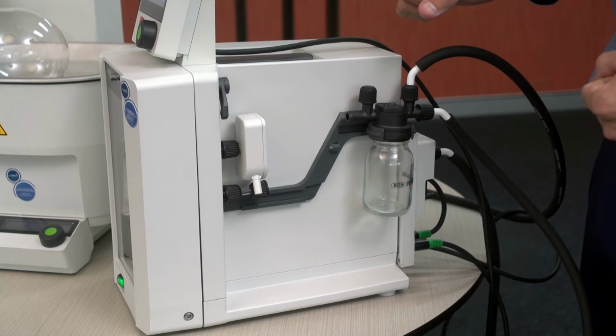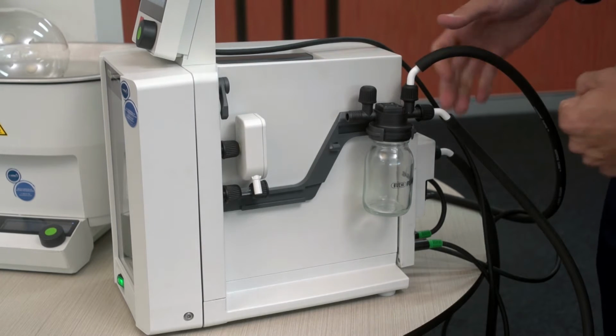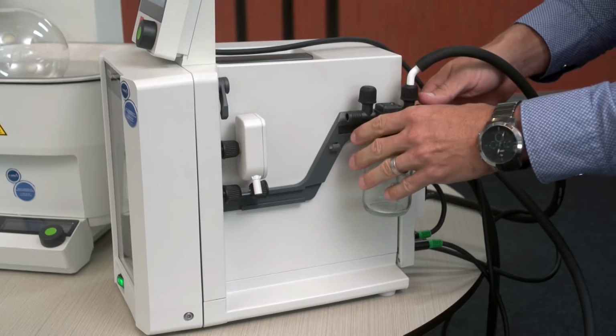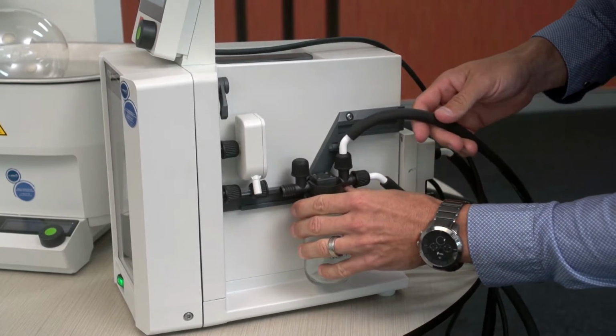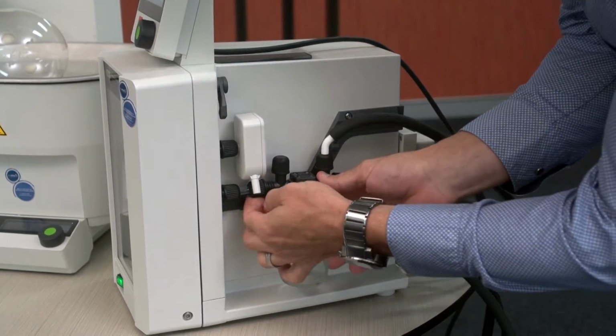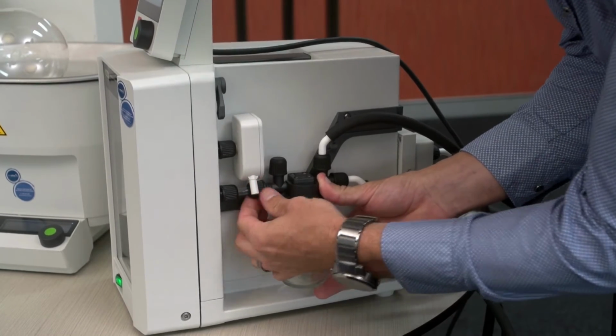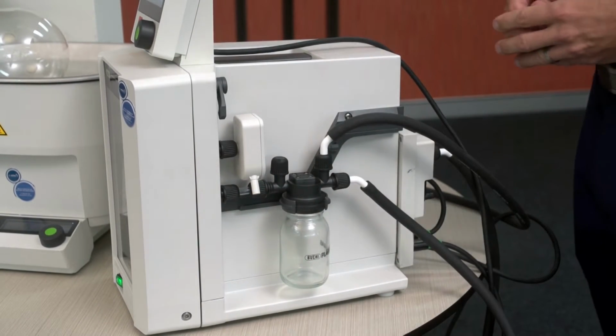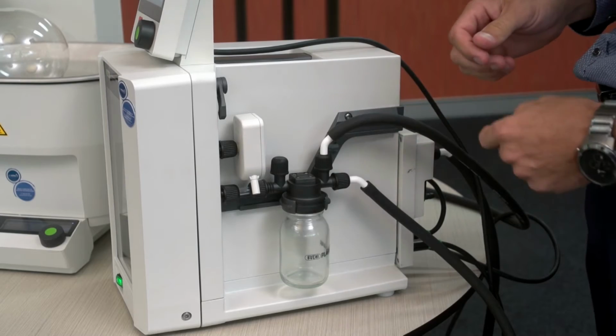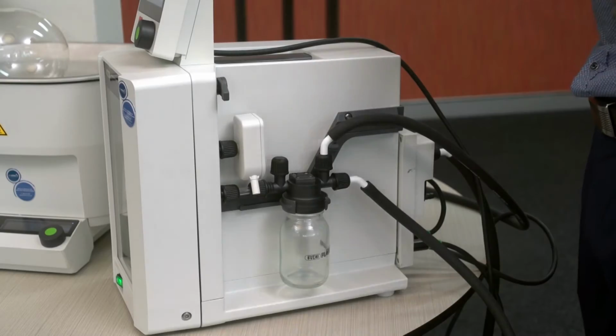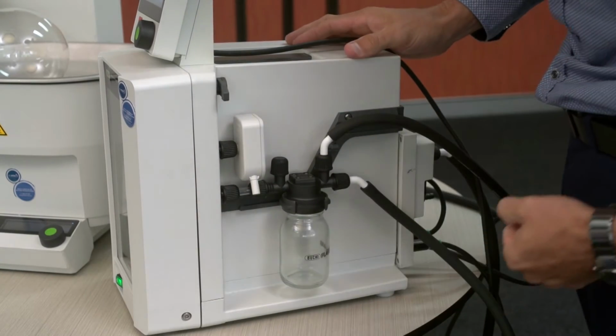Buchi have designed the inlet and the outlet in close proximity on the left-hand side. They've also redesigned the way that the Woulff bottle is integrated onto the pump by easy slide on, sitting down here just in front of the pump inlet. Slides in and connects as such. Buchi have also fitted a redesigned silencer, which is nicely fitted on the left-hand side, and also an integrated gas ballast to eliminate any condensate which could build up on the pump heads.